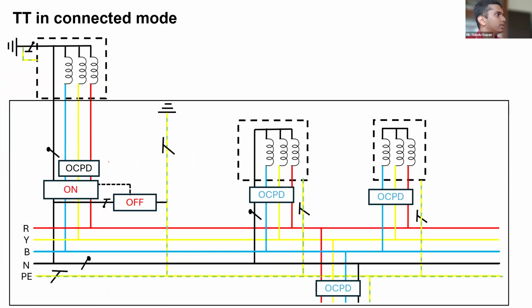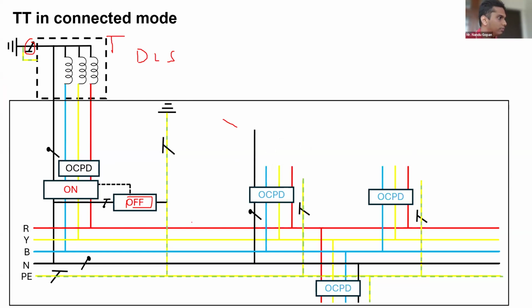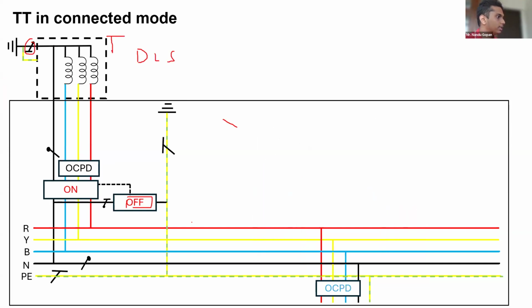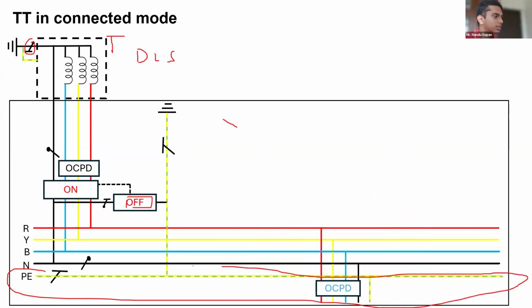This is it in TT in connected mode. This will be a TT system. So what happens is there will be a transformer. Discom is working. This is in TT source. So we can consider this off. We can consider this off. There is already a system referencing over here. The T is already done here. And since this is off and this is on, we can take these things out. So what it shows is T is done here, and the P of this installation has been connected to another earth electrode. This is another T. So this will be a TT system in connected mode.